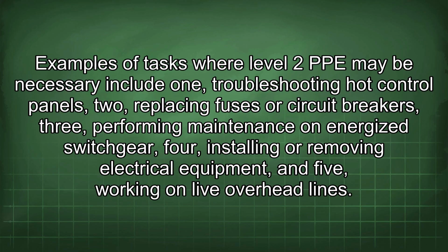Examples of tasks where Level 2 PPE may be necessary include: 1. Troubleshooting hot control panels, 2. Replacing fuses or circuit breakers, 3. Performing maintenance on energized switchgear, 4. Installing or removing electrical equipment, and 5. Working on live overhead lines.